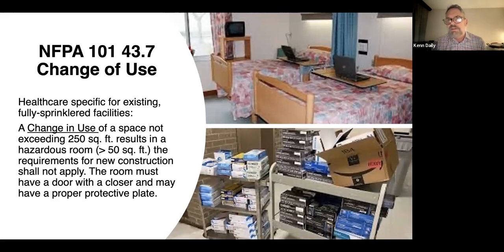You don't have to guarantee that the walls are 1-hour rated, and you don't have to put a 45-minute door on. You only have to add an automatic closer to that door. In existing nursing homes, since we were fully sprinkled, we do get a little bit of benefit there.